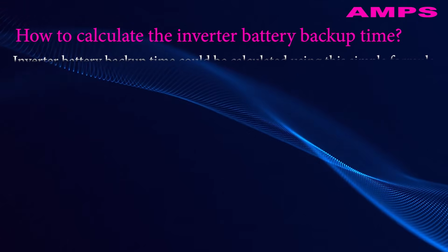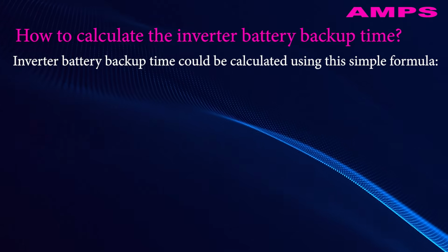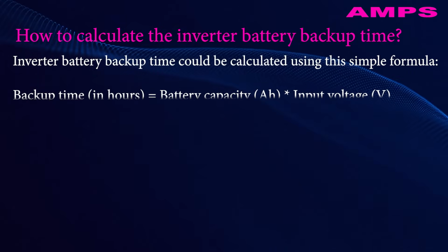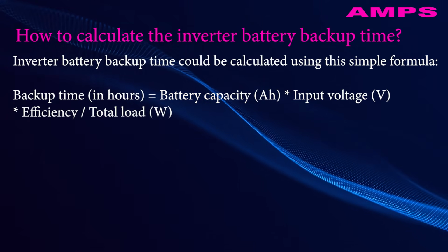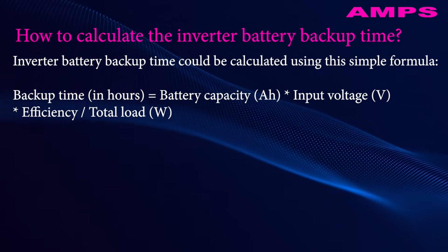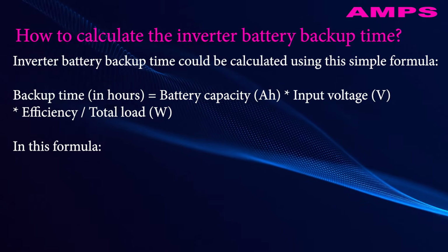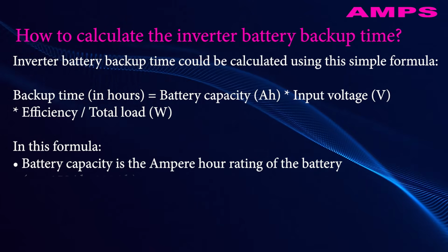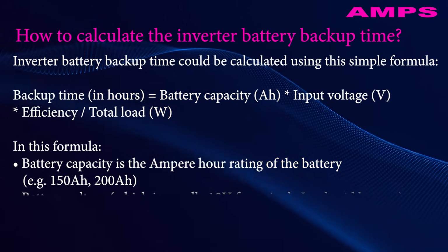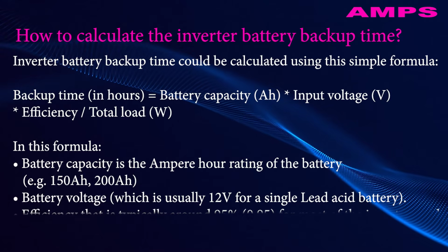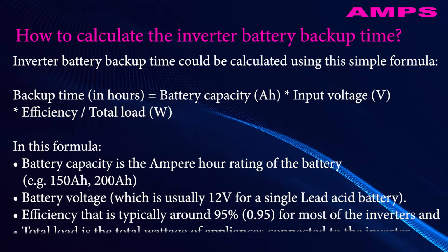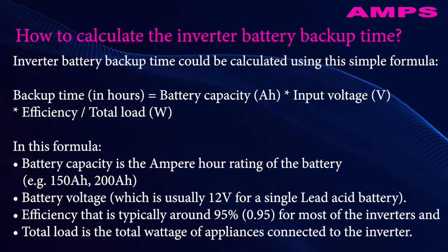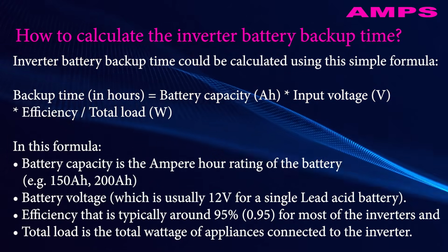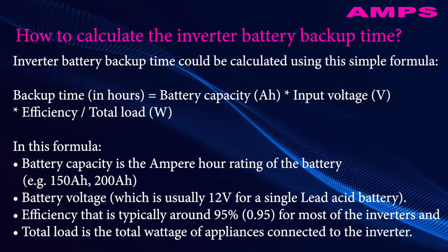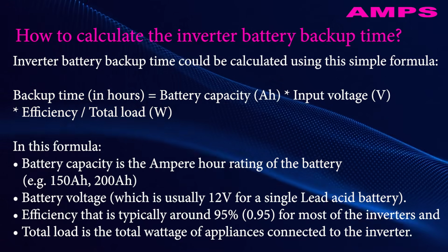How to calculate the inverter battery backup time? Inverter battery backup time can be calculated using this simple formula. Backup time, in hours, equals battery capacity, Ah, times input voltage, V, times efficiency, divided by total load, W. In this formula, battery capacity is the ampere-hour rating of the battery, e.g. 150 Ah, 200 Ah. Battery voltage is usually 12 V for a single lead-acid battery. Efficiency is typically around 95%, 0.95, for most inverters, and total load is the total wattage of appliances connected to the inverter.